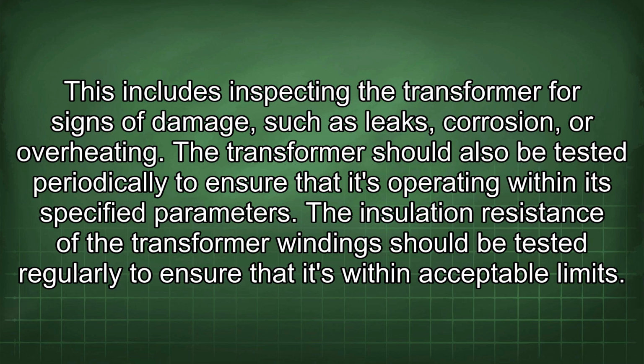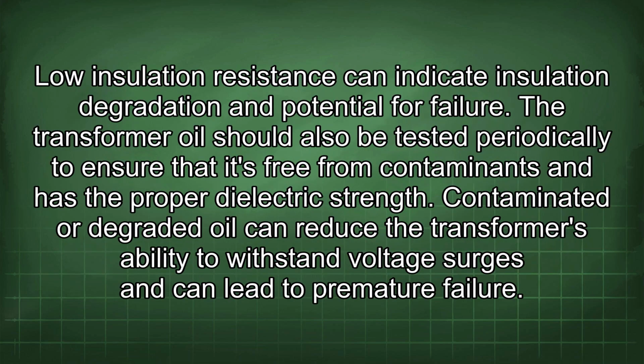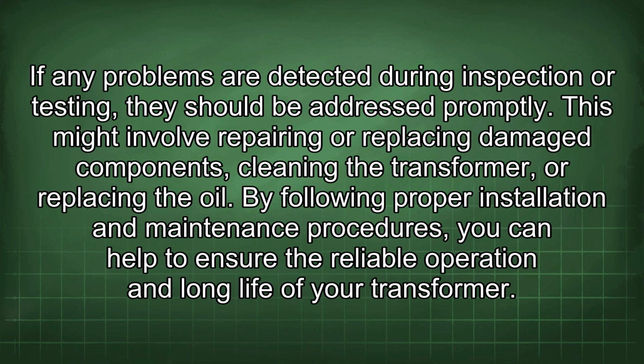The insulation resistance of the transformer windings should be tested regularly to ensure that it's within acceptable limits. Lower insulation resistance can indicate insulation degradation and potential for failure. The transformer oil should also be tested periodically to ensure that it's free from contaminants and has the proper dielectric strength. Contaminated or degraded oil can reduce the transformer's ability to withstand voltage surges and can lead to premature failure. If any problems are detected during inspection or testing, they should be addressed promptly. This might involve repairing or replacing damaged components, cleaning the transformer, or replacing the oil. By following proper installation and maintenance procedures, you can help to ensure the reliable operation and long life of your transformer.